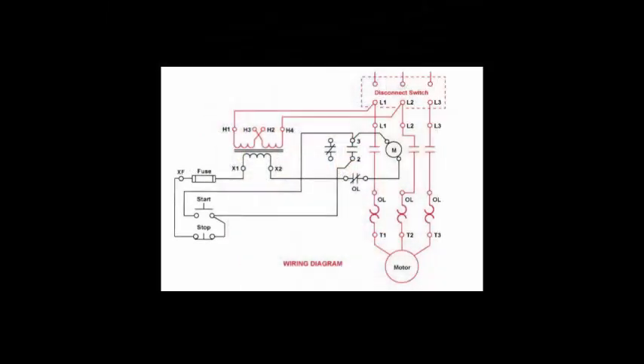circuit next. This is the wiring diagram, motor starter circuit, and we were just looking at this starter right here in this area, and what we have here is the power coming in on these three terminals, L1, L2, and L3. Then we have the coil here, and this coil will close these three contacts for the A, B, and C phases. It will also close this contact here, which is an auxiliary contact. After the voltage goes through the contacts, it comes down to the overload relay. If any of these phases, or all three of them, gets too hot, this contact here will open up. Then after the voltage goes past the overload relay, it goes out to the motor.